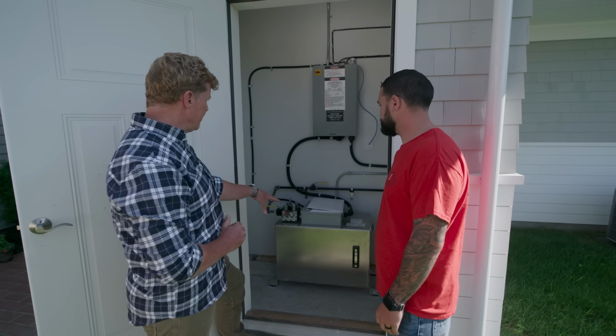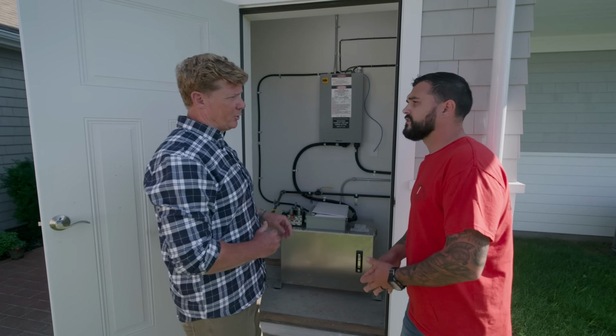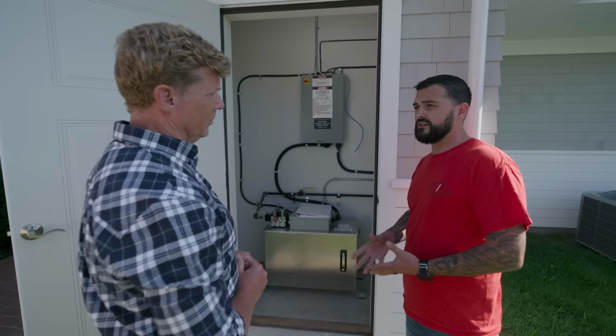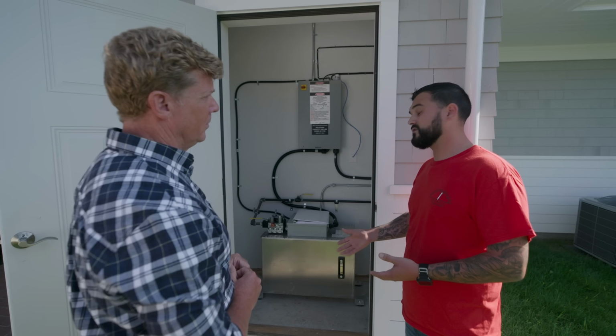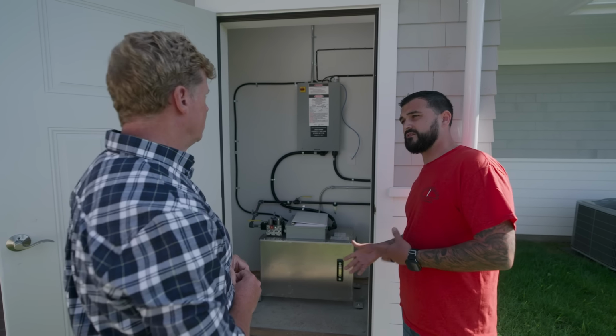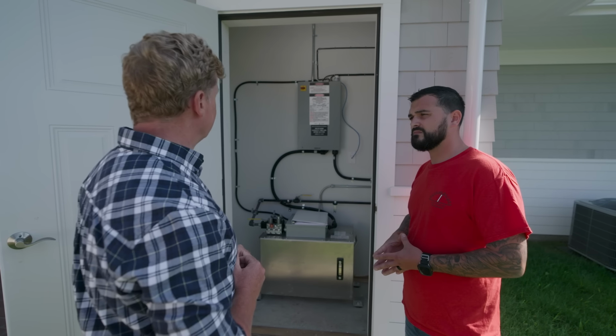So we have a pump, which means we need power. What do you guys have to put in for electric? You need a 240 circuit fused at 30 amps, and also a 120 circuit fused at 15 amps. That's not too bad, not uncommon.